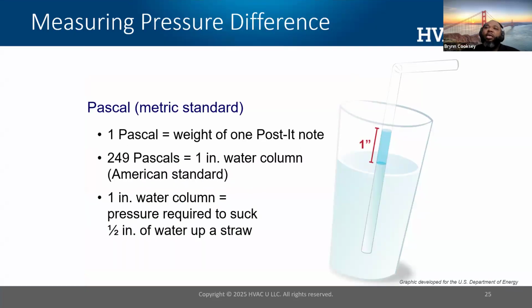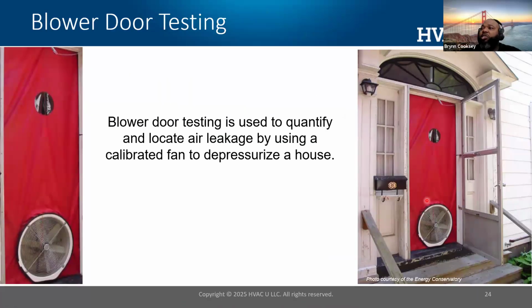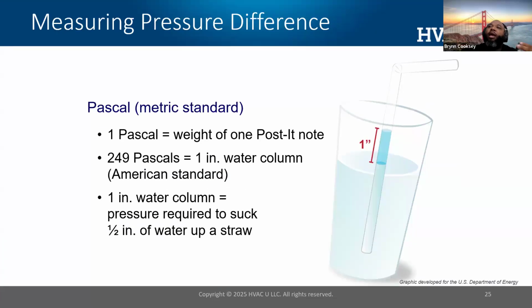Now, a blower door test is a test that simulates a 15 to 20 mile per hour wind. When you run a blower door, the airflow hits the building at the surfaces, and it comes in through the gaps, cracks, and holes of the building shell. And the way it works, when I run a blower door, as the air is discharged out of the blower door, buildings have this relationship. If I take air out of the building, air has to come into the building. And as a result, I have a test pressure. That test pressure we rate in pascals, right?